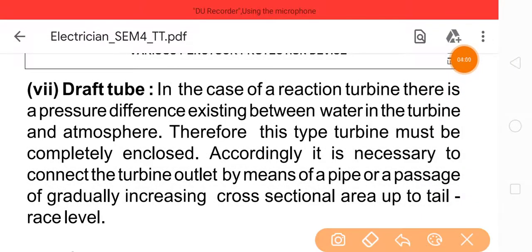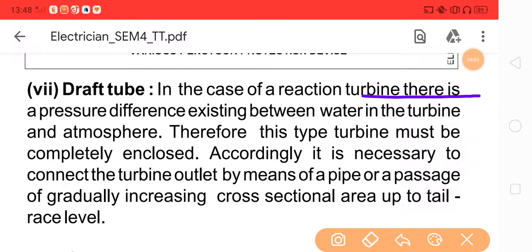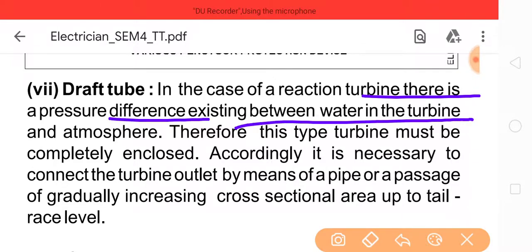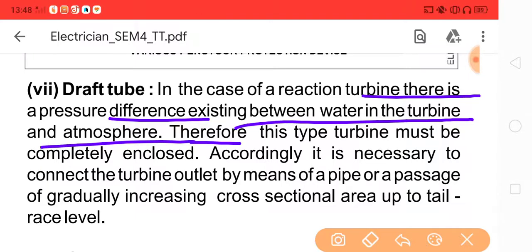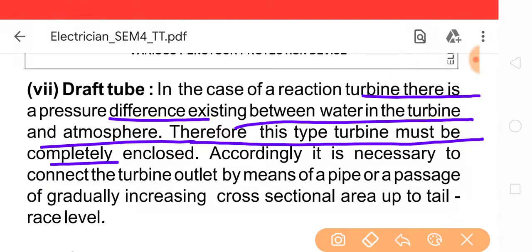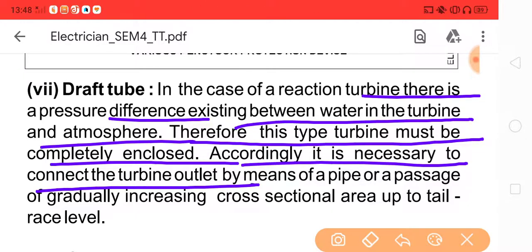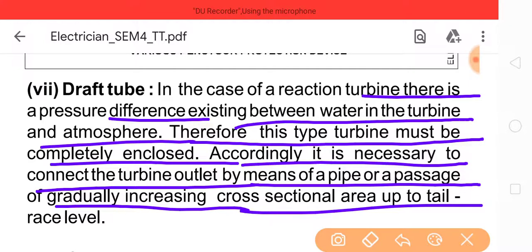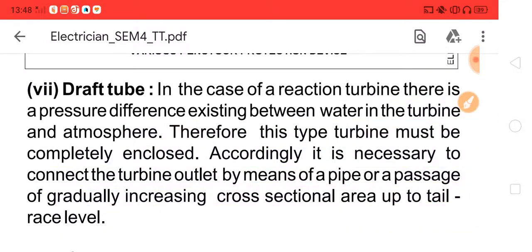Draft tube. In the case of a reaction turbine, there is a pressure difference existing between the water in the turbine and the atmosphere. Therefore, this type of turbine must be completely enclosed. Accordingly, it is necessary to connect the turbine outlet by means of a pipe or passage that gradually increases in cross-sectional area to the tail race level.